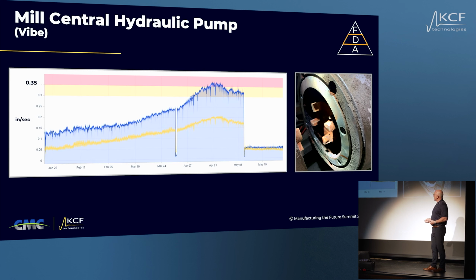Another one, again, another defect, mill crane central hydraulics. You can see over time we're getting an increase in vibration. We hit the alert, and then we shut the pump down, split the motor and pump, and we found that the rubber insert between the two coupling halves had disintegrated, so we were running metal to metal on the two coupling halves. Again, a quick fix: split it, reinsert the insert, bolt it back up, and we're back to normal levels.